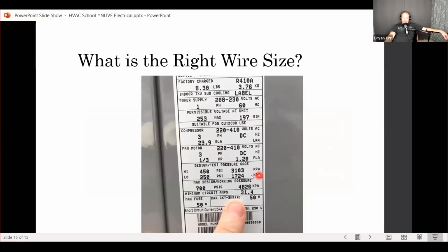This is another example. So here's a Carrier. This is actually my house. We have a 50 amp breaker, and that's what I've got in my panel. And in this particular case, a number 10 wire is actually acceptable given the type of wire and the insulation rating on the wire that's being used and all that other stuff. So on my house, I've got a 50 amp breaker and a number 10 wire running to my condenser. Hopefully you don't hear the fire trucks from your house when my house burns down. No, the point is that this is allowable, based on the National Electrical Code, Section 440 of the NEC.